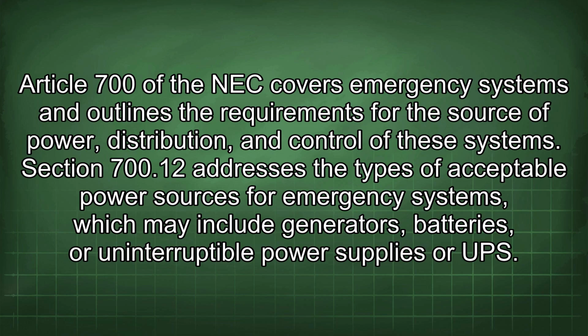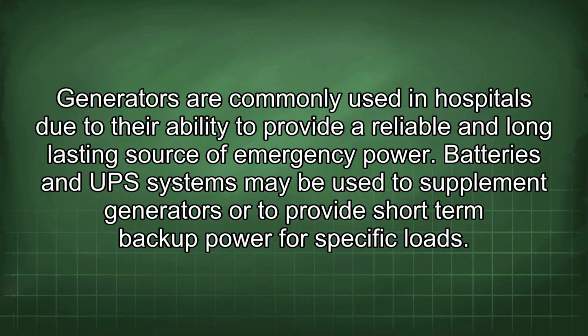Article 700 of the NEC covers emergency systems and outlines the requirements for the source of power, distribution, and control of these systems. Section 700.12 addresses the types of acceptable power sources for emergency systems, which may include generators, batteries, or uninterruptible power supplies, or UPS. Generators are commonly used in hospitals due to their ability to provide a reliable and long-lasting source of emergency power. Batteries and UPS systems may be used to supplement generators or to provide short-term backup power for specific loads.